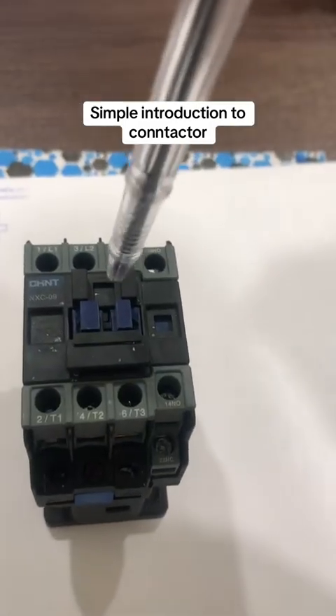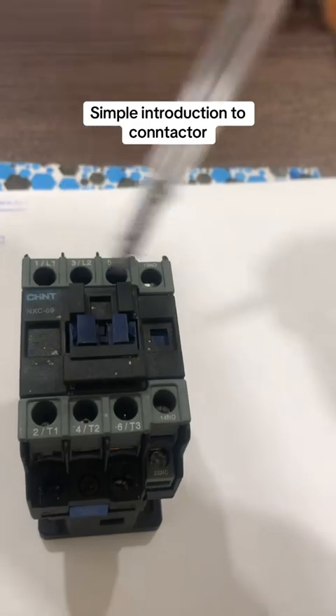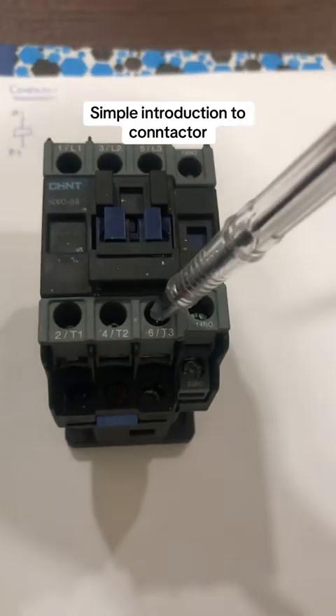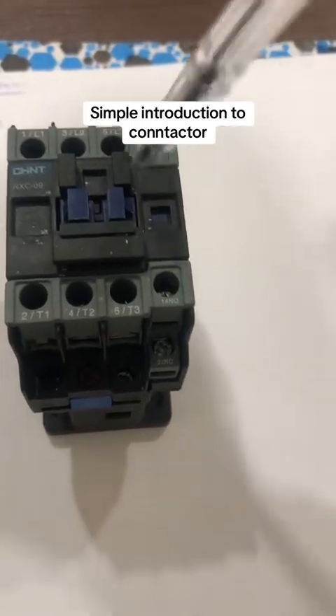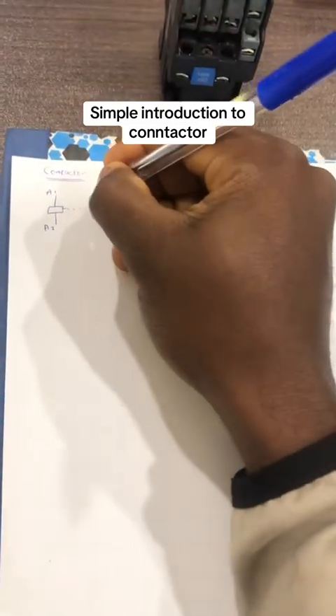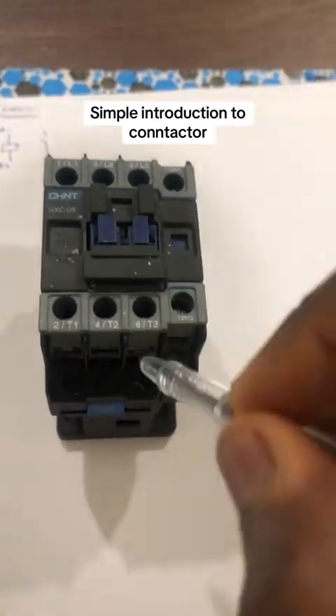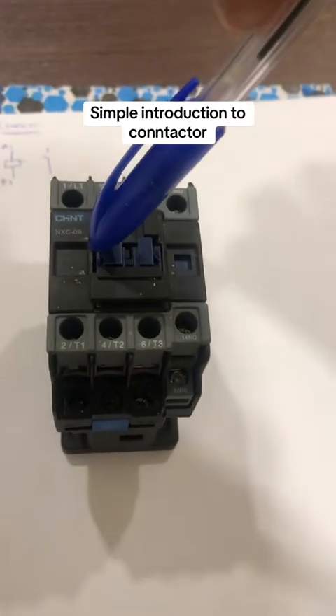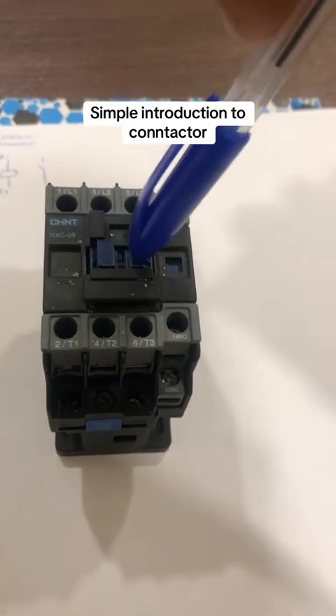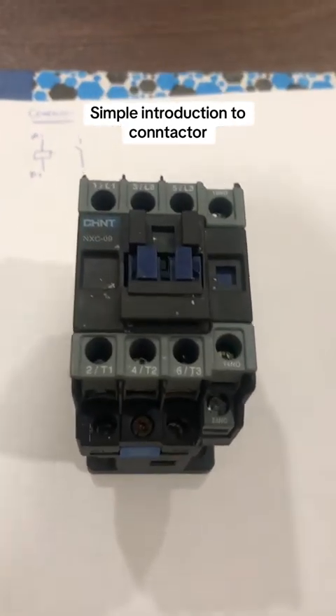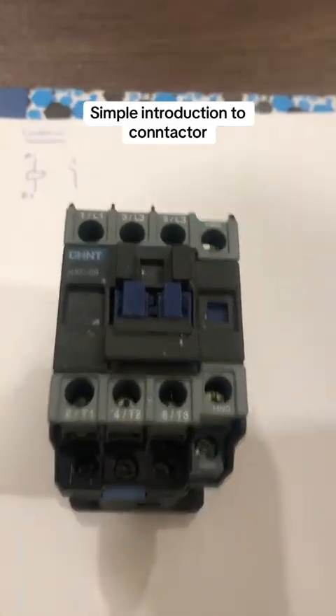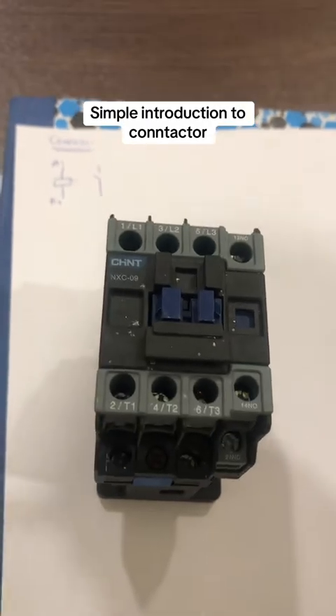This contactor, like I said, has the power contacts, which are these three, and also the control contact, which is this one alone. So now we would represent these contacts with this, because everything you are seeing here are normally open contacts. All of them are normally open contacts. It's been designed in such a way that there is what we call an auxiliary contact, which you can make use of when you are in need of more contacts.